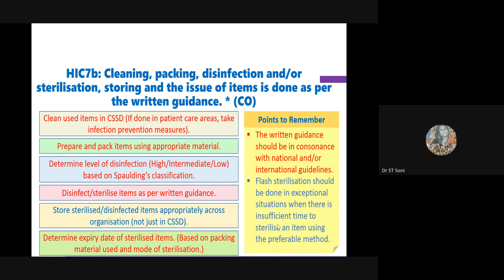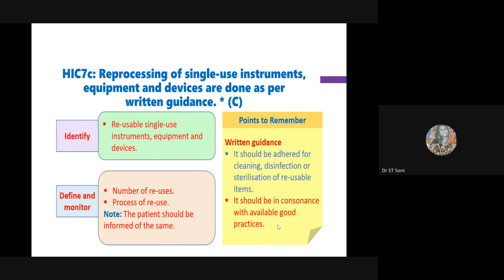Okay, and also the validation of the entire process needs to be done. And if you are using a single use device, you need to mark how many times you can use it, which method you will be using, and it should be in consonance with the good practices. So validation can be physical daily, so you can monitor the temperature, pressure, chemical strips, and at least weekly bacteriological. Engineering validations are the Bowie-Dick test, or we say it as the load test and the leak test.